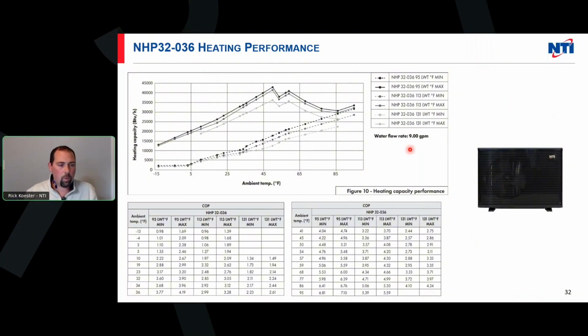So when you look at our performance charts right off the bat for heating, you can see this is going to be our 3-ton system. There are 3 solid lines and 3 dashed lines underneath it. The solid lines, each shade of them, represent a different temperature. In this case, we use 95, 113, and 131 degrees Fahrenheit leaving water temp. I'm looking at the max the system can produce at that ambient temperature, and the minimum the system can produce at those ambient temperatures.